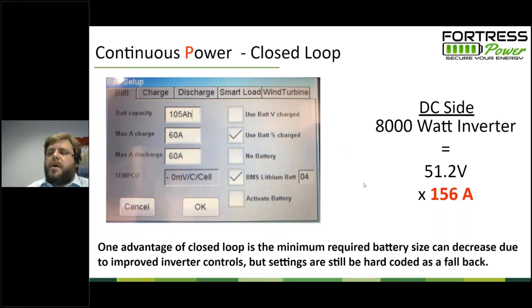And this is also a reason why we put a lot of emphasis on closed loop programming, because there's a large customer base out there, particularly those who are not losing power frequently and therefore having to live with their systems in an off-grid mode of operation frequently, but instead customers who just want the batteries there for some time of use metering or some rate optimization, and they only want a little bit of backup power, not a whole bunch of backup power, a couple of hours of backup power rather than a day's worth of backup power.